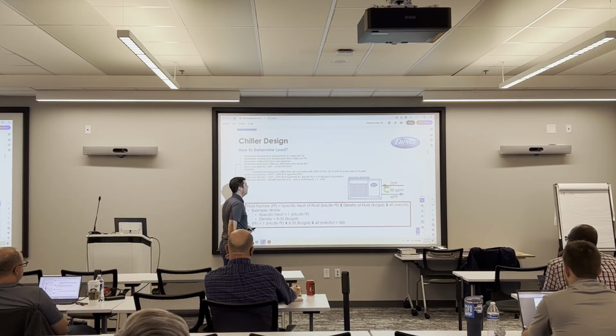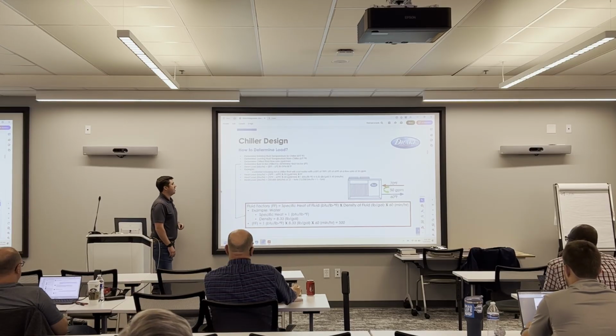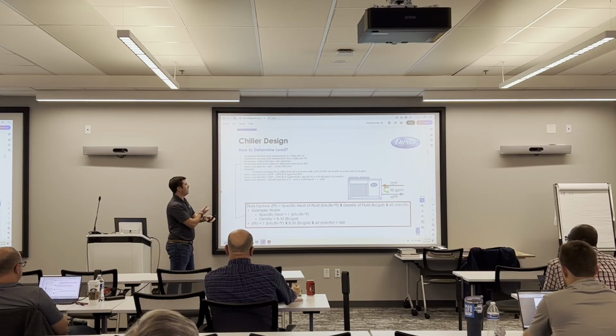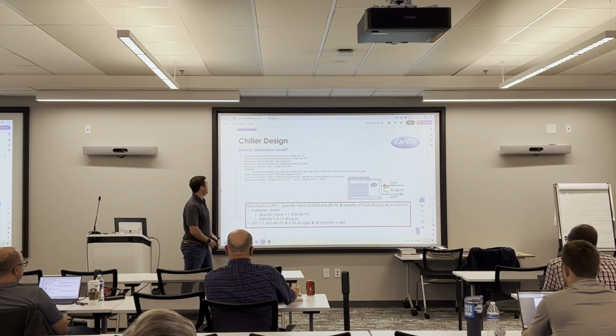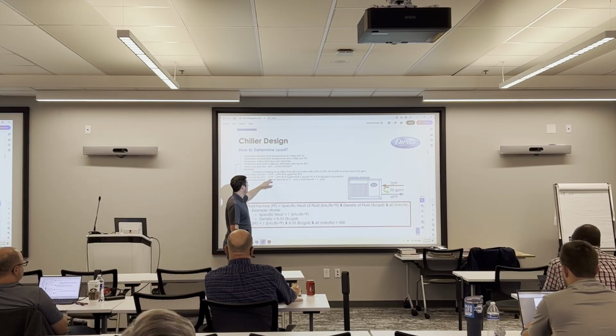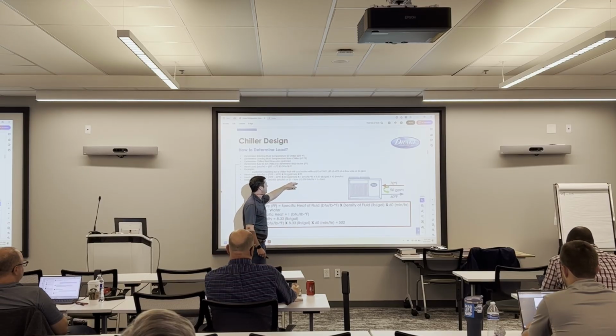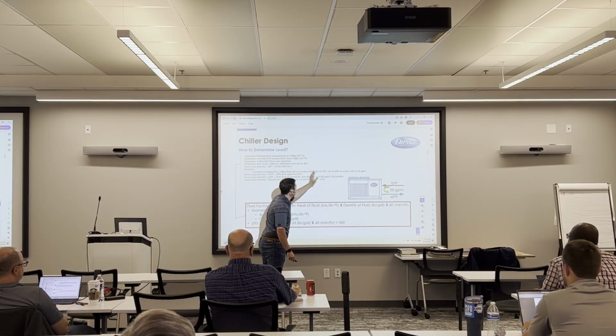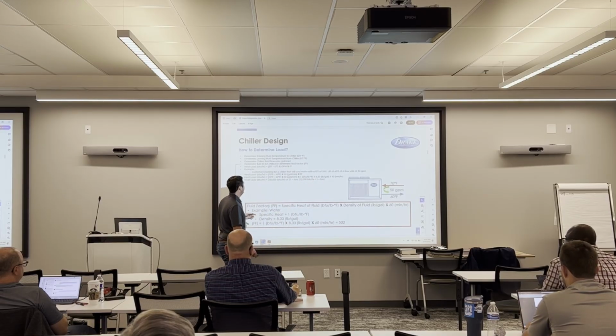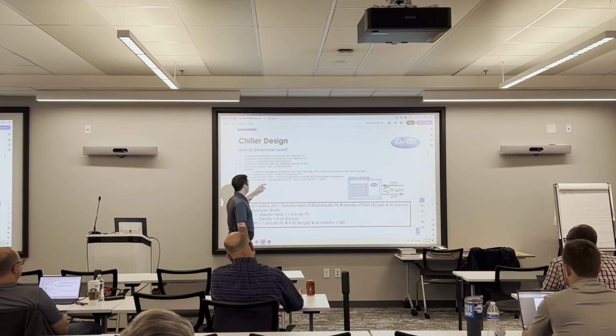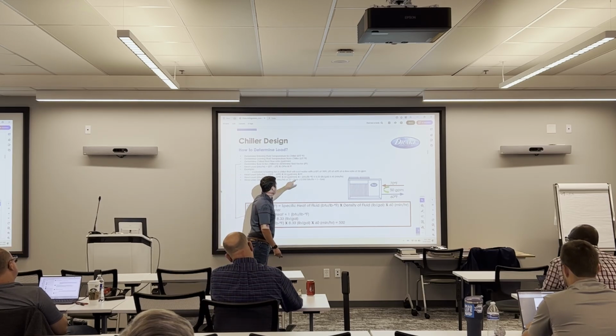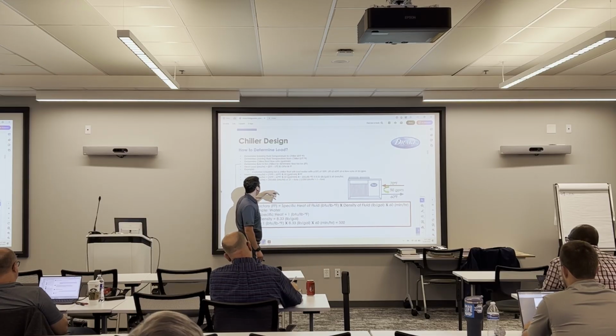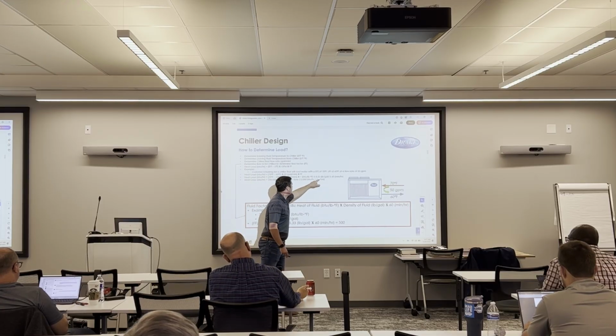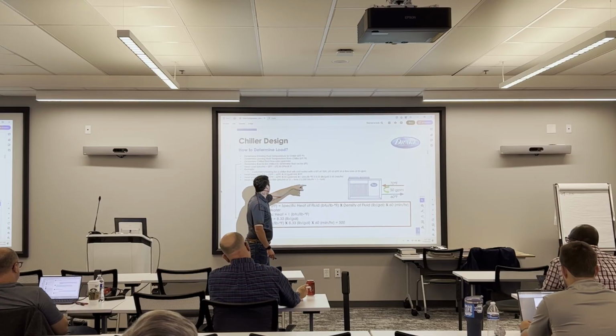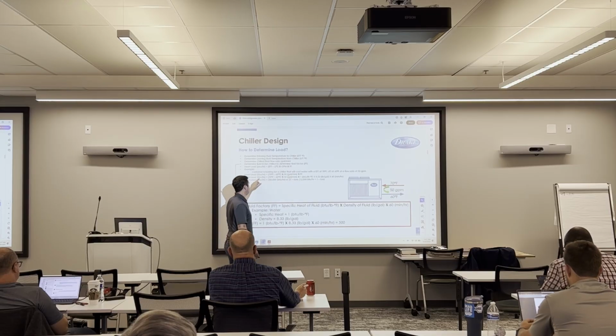One ton is equivalent to 12,000 BTUs per hour. But you can see how this equation works because all the units cancel out. It's what I call a sanity check. You'll have temperature times gallons per minute times BTUs per pound per degree times pounds per gallon times minutes per hour. Your temperature is going to drop out because it's getting divided out by the temperature from your specific heat. Your gallons per minute is going to cancel out with your density. And then your time factor is going to be canceled out by your minutes and the GPM, and you're left with BTUs per hour.